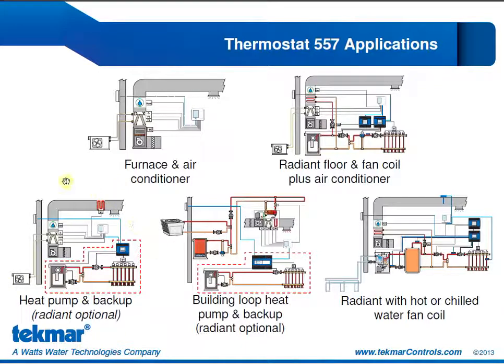Our first heat pump application shows including the option of a radiant floor, and that's why it's outlined in the dashed red line. It is optional. If we do include the radiant, that is our first stage of heat. Our heat pump can provide an additional 2 stages of heat, and we have an electric strip backup which can provide a 4th stage of heat. When we switch over to cooling mode, our heat pump can provide up to 2 stages of cooling. Again, we have the humidifier in the ductwork for humidity control.